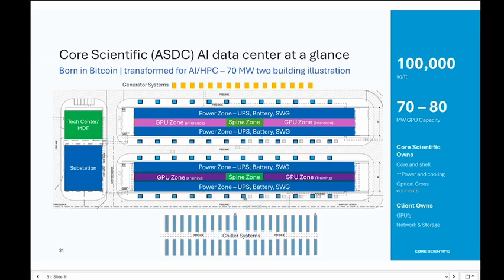We have medium voltage distribution transformers, so our medium voltage runs from the substation to the buildings. Then we add in our ASIC miners, our switchgear, and our PDUs to power those miners. We have two big cold aisles on each side of the building and one big hot aisle to allow for airflow and exhaust. So this is essentially what a Bitcoin mining facility looks like today for us.